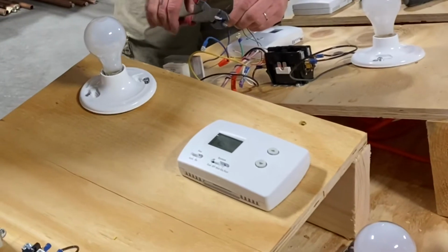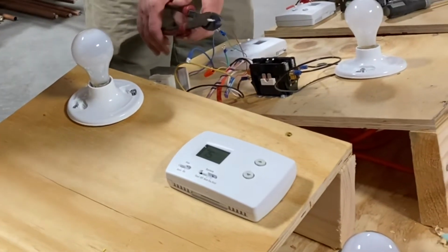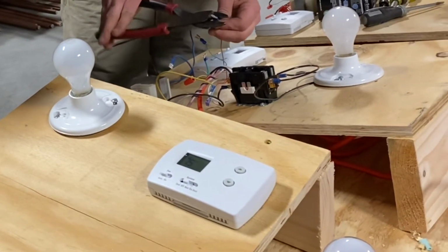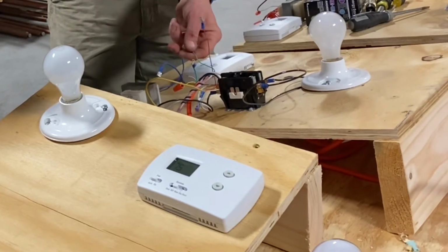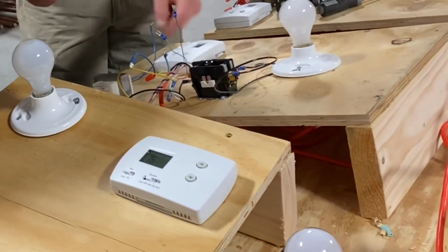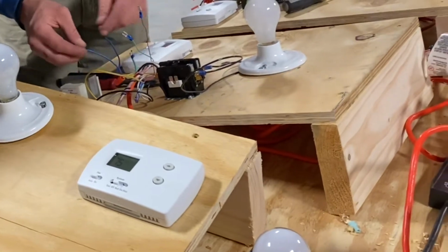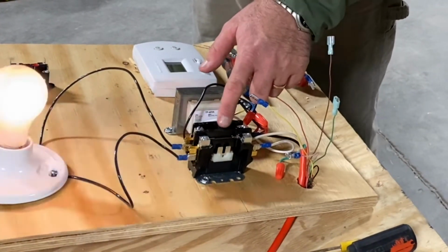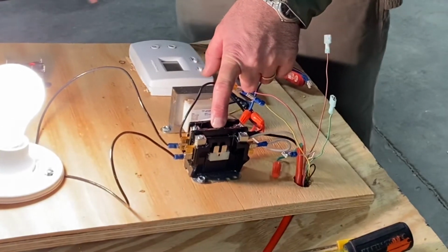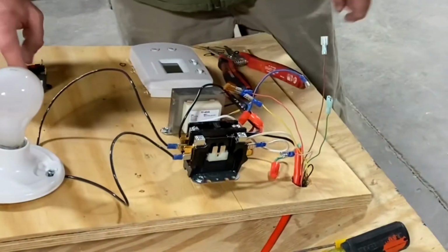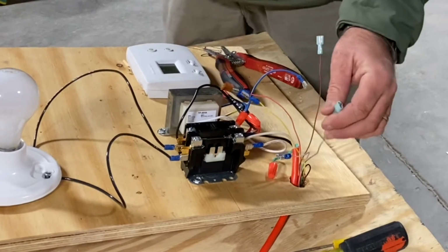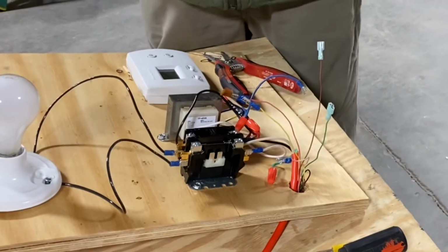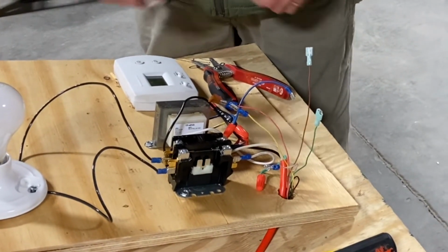What we would like to happen is for our thermostat in cool mode, we know that our yellow wire operates our compressor contactor, and this is the compressor contactor. So we want to wire this with our low voltage controls such that when we turn the thermostat to cool, this comes on for cool, and then we want to add another one - the green wire will turn the next light on, and it'll simulate our fan operation.